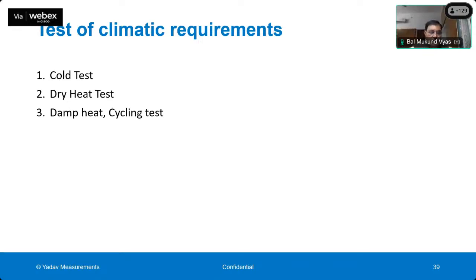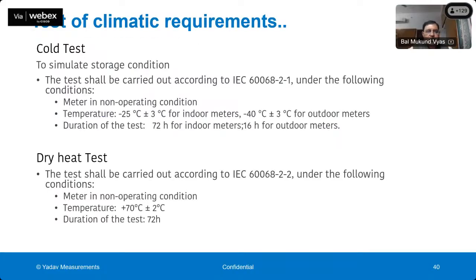So, damp heat tests. The two tests, cold and dry, actually simulate the storage conditions. When the meter is being transported or stored, suppose you are transporting the meter through ship or through air, it can face temperatures as low as -25 degrees centigrade and as high as 70 degrees centigrade. But of course, when the meter is being transported, it is not in operating conditions. So the cold and dry tests are done with the meter in non-operating conditions, so no voltage or current is applied to the meter.